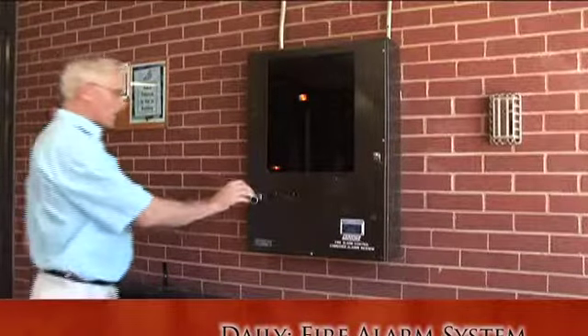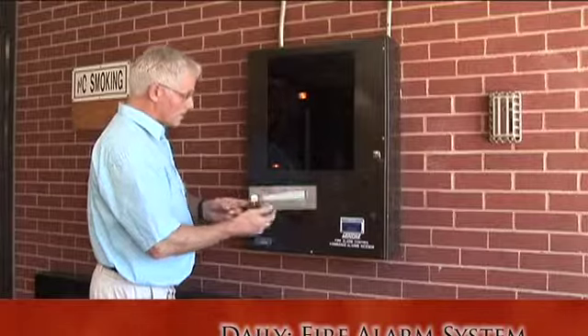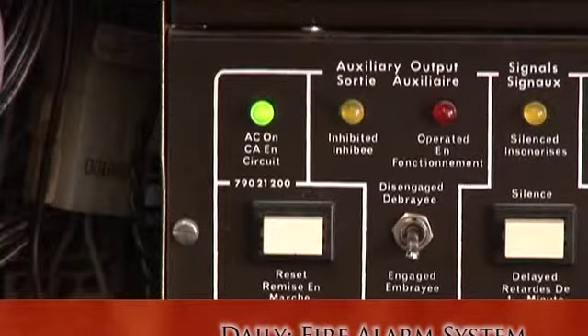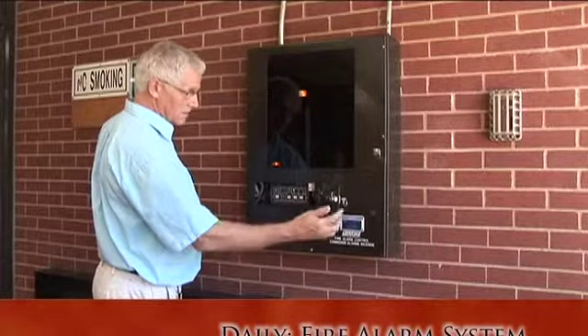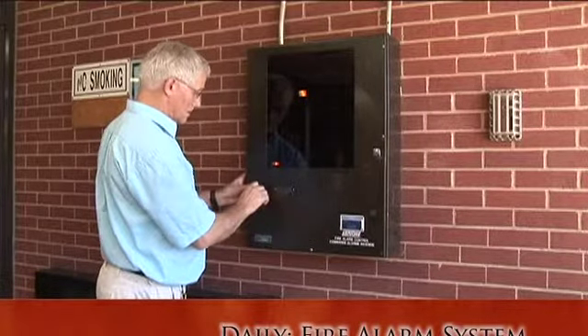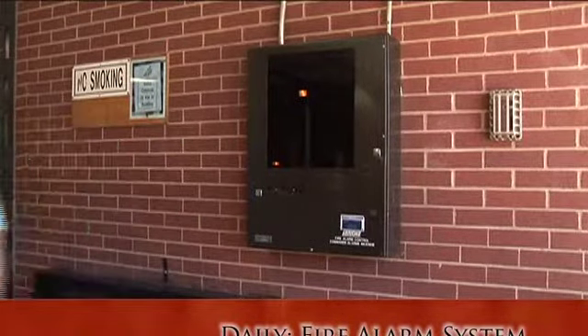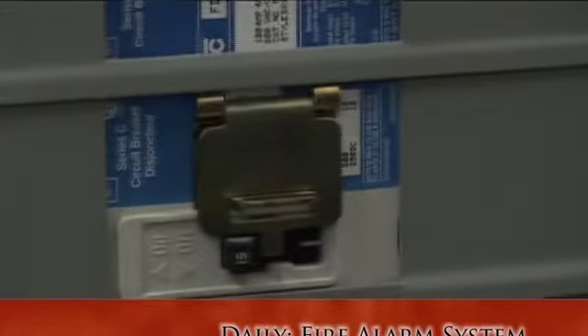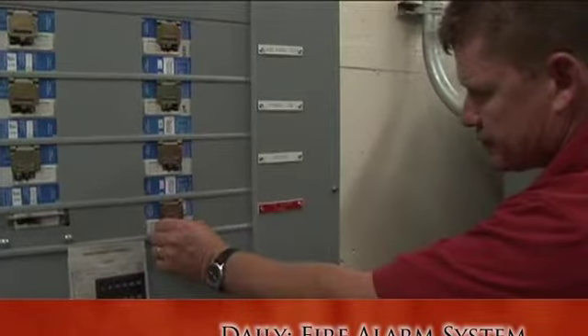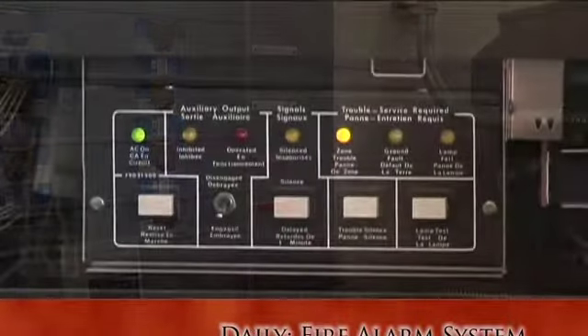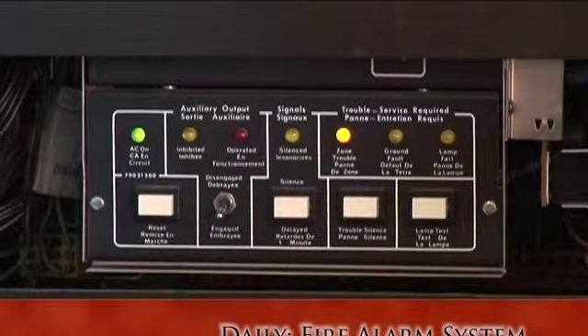The school's fire alarm panel should be visually inspected daily to make sure the AC power lamp is illuminated and to determine if there are any trouble signals. If the AC power lamp is off, some panels may have a lamp test switch to verify that power is connected. Failure of the lamp to come on indicates that the AC power to the system has been interrupted. At this point, check the fire alarm system AC breaker or call your supervisor. If any lamps beside the AC power on lamp are illuminated, note the lamp description and advise your supervisor immediately.